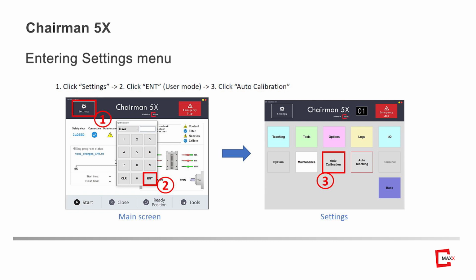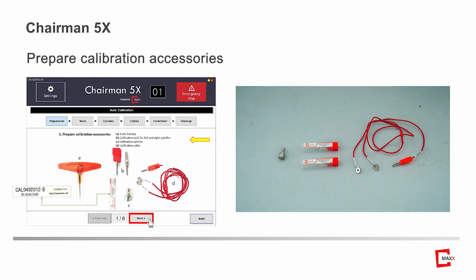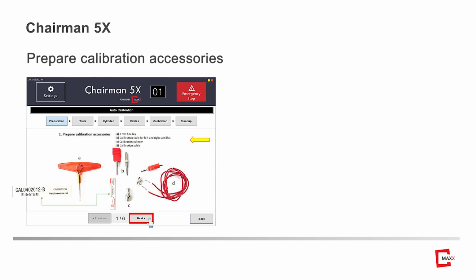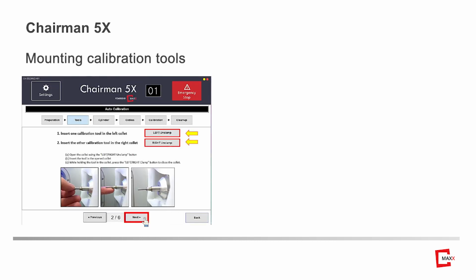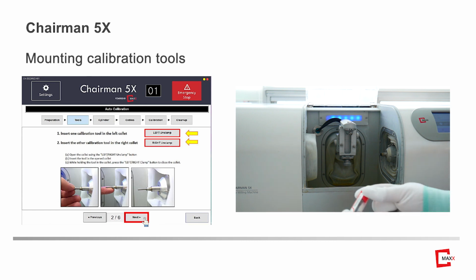To do auto calibration, please go to Settings. Click Enter and then click Auto Calibration. Step 1. Prepare calibration tools, signal cable, and calibration cylinder, also known as a calibration jig. When it's ready, please click Next to continue.